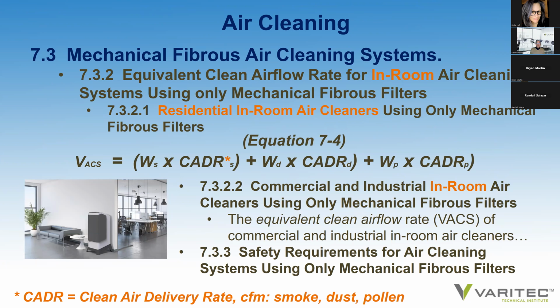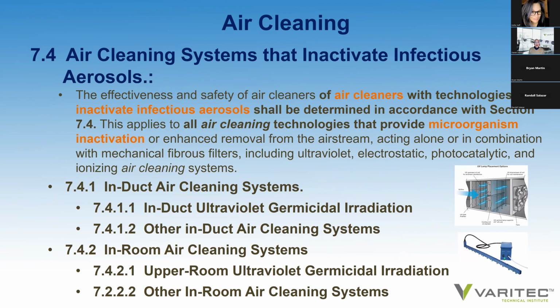Mechanical fibrous air cleaning systems can also be in-room. There can be HEPA, portable cabinet HEPA units that are actually used. There are residential in-room cleaners, and all of these are given effectiveness at air cleaning equations to determine how much clean air is provided to a zone, to see if it's in conformance to the equivalent clean air required by the standard.